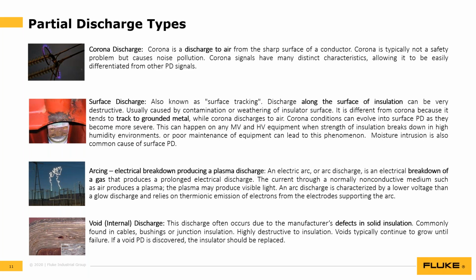Corona, and this is a type of discharge. Often by itself, it's not a safety problem or a degradation of the equipment. It's more of noise pollution. It does cause some reduction in the power generation there, but it's usually not something that people worry about. Surface discharge, on the other hand, is also called surface tracking, and it definitely is one of the larger issues. You can see it visually sometimes, but it comes from contamination on the insulator surface. So once there's a way for that energy to go across, it can damage there.